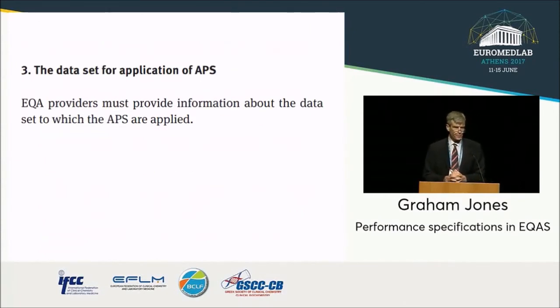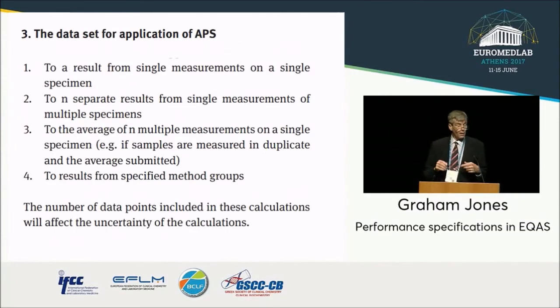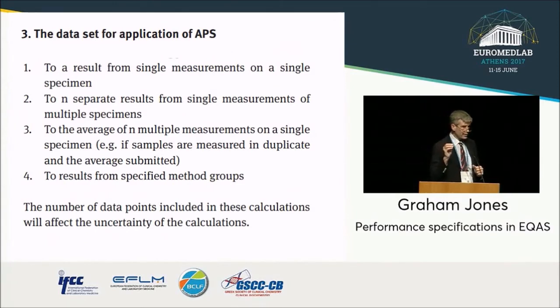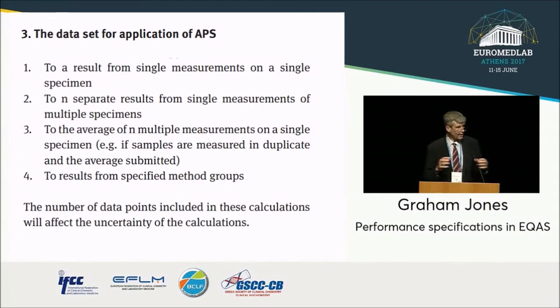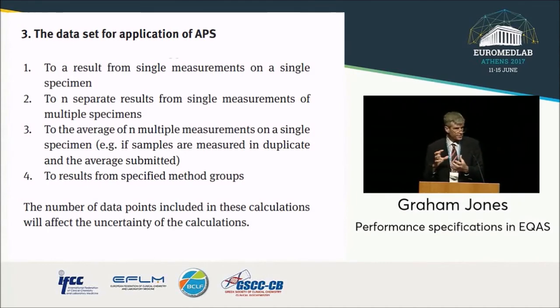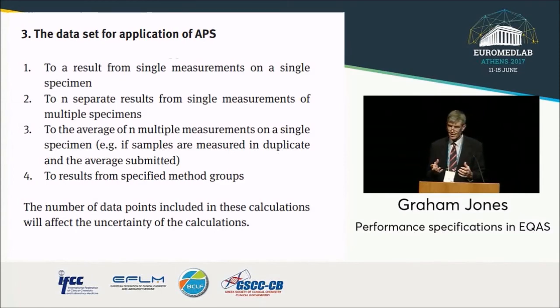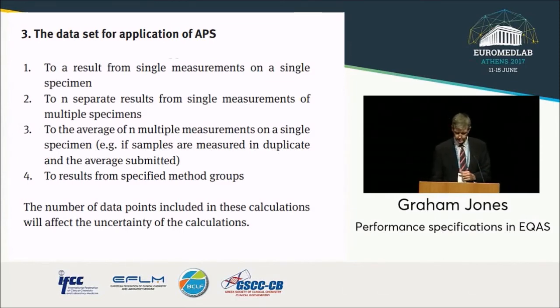The third element is the data set for the application of the analytical performance specifications. Is it applied to one sample or multiple samples? If you've measured something multiple times and taken an average, that requires different performance specifications than just a single measurement. If more than one sample is used and any statistics have been applied, such as taking an average or calculating a standard deviation, knowing how that process has been done is required to fully understand the EQA process.